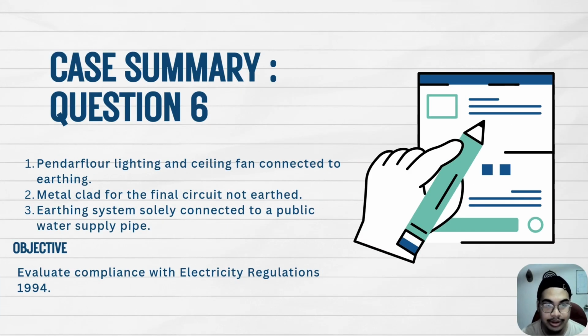Based on question 6, here is the summary of the question: pendant floor lighting and ceiling fan connected to earthing; the metal clad for the final circuit not connected to earth; and the earthing system solely connected to the public water supply pipe. Our objective for this case study is to evaluate compliance with Electricity Regulation 1994.